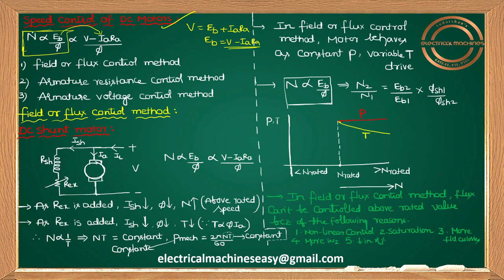If you want to control the speed of a DC motor, that can be done by controlling flux — this is called the field or flux control method. Speed can also be controlled by controlling armature resistance — this is the armature resistance control method. Third, speed can be controlled by controlling armature voltage — this is the armature voltage control method. In this video, I'll discuss the field or flux control method.